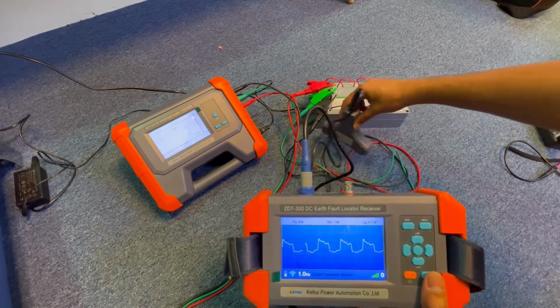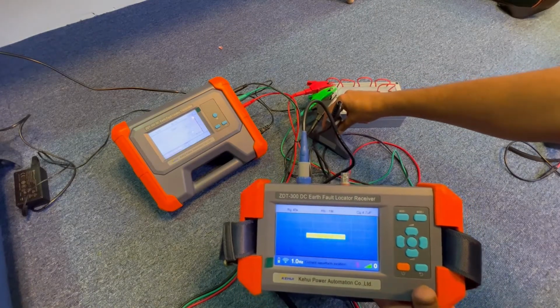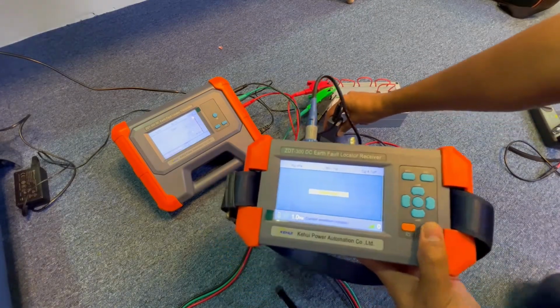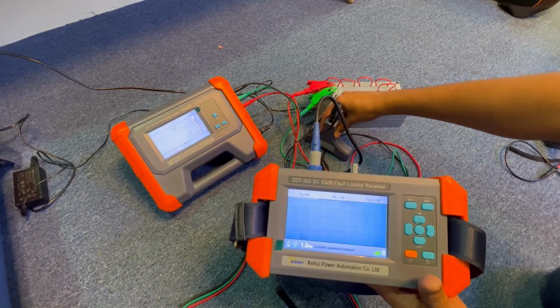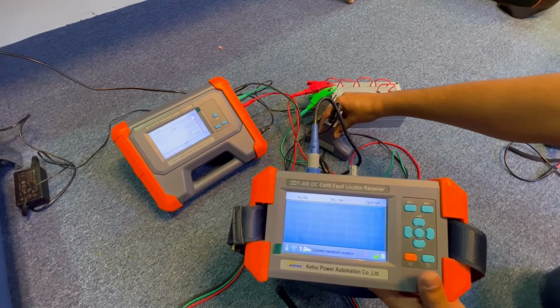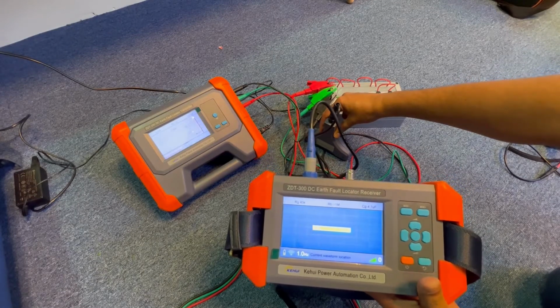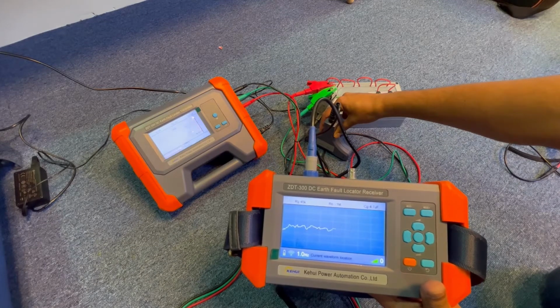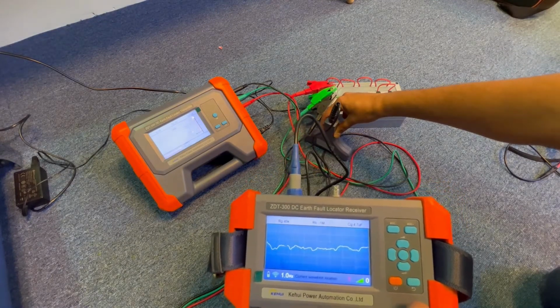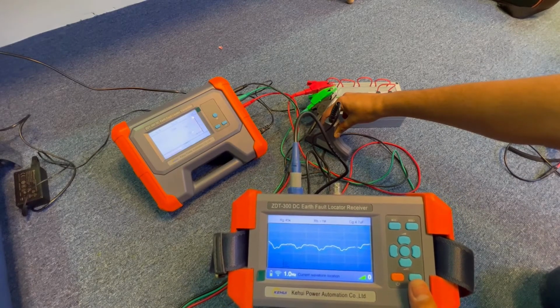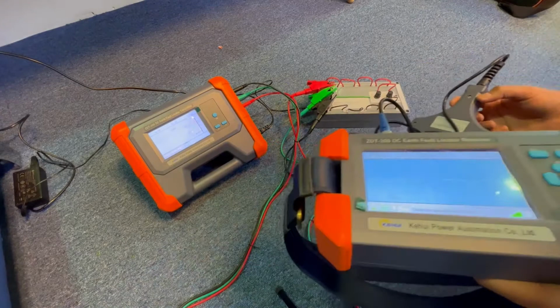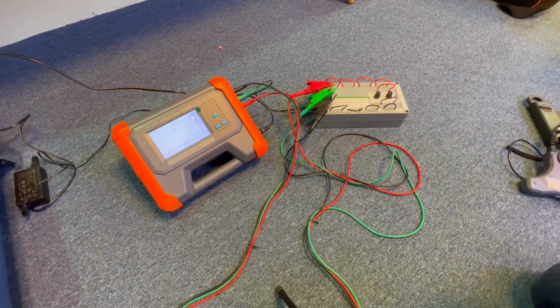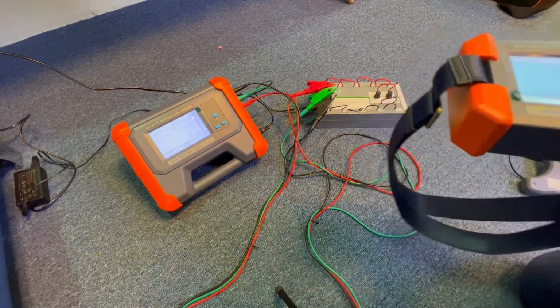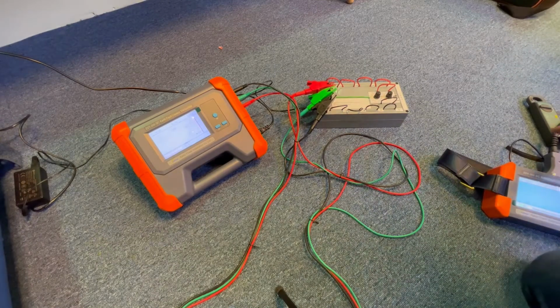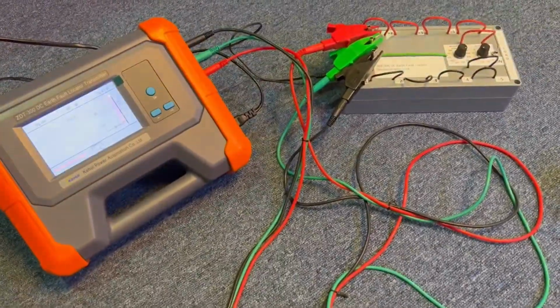Then let's keep it on the negative. Okay, and then refresh. There's no fault, no signal. Again refresh. No fault, no signal. So this clearly states how these sensors work in different conditions, faulty and healthy conditions. This is how this equipment helps you to exactly pinpoint the fault and trace the faulty feeder, and without interrupting the DC system, you can make the system stable.